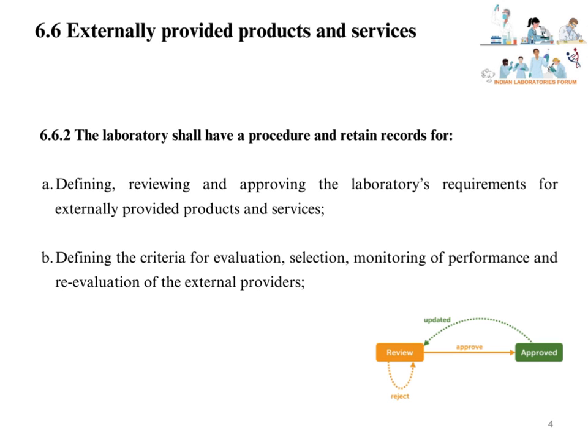For example: subcontracting labs should be ISO/IEC 17025 accredited. Similarly, calibration labs should also be accredited as per ISO/IEC 17025. Proficiency testing providers should be accredited as per ISO 17043, and reference standard providers should be accredited as per ISO 17034 or be a competent producer. Disposal agencies should be pollution control board approved. The laboratory must also define evaluation criteria such as quality of products received, critical consumable checks, receipt conditions, packaging condition, delivery time, etc.